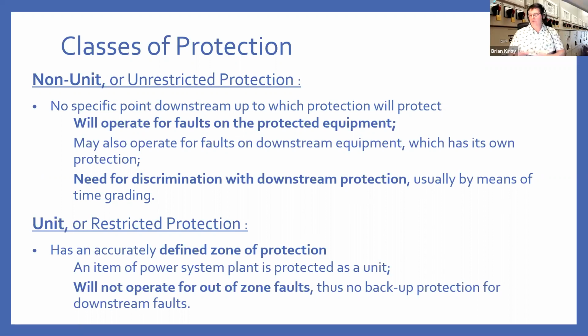So in this case, say you've got a three-stage protection scheme. Each stage will have its own protection zone, overlapped, of course, so there's no bits that are missed by the protection. And then each zone will only operate if there's a fault. So if in zone 1 there's a fault, zone 3 will say, that's not in my zone, so I don't care, I will keep operating. And this is more commonly used in the transmission systems. Non-unit tends to be used more in distribution at lower voltages, but non-unit protection also tends to be your backup fail-safe in case your higher level protection has failed.